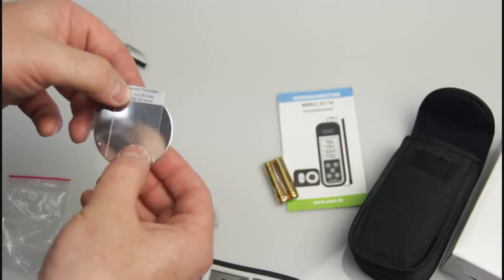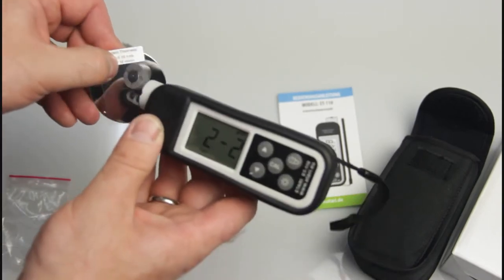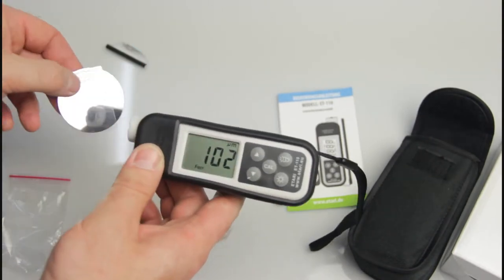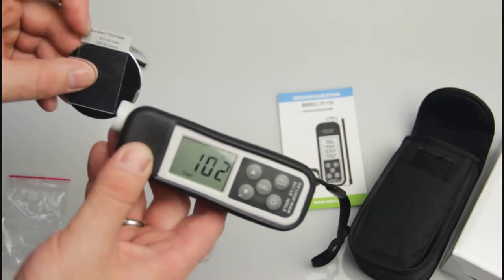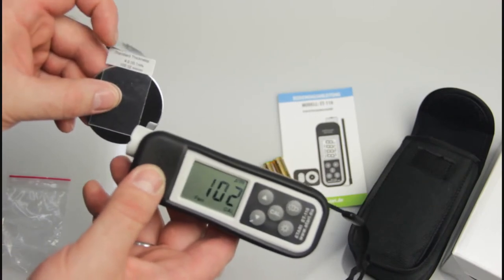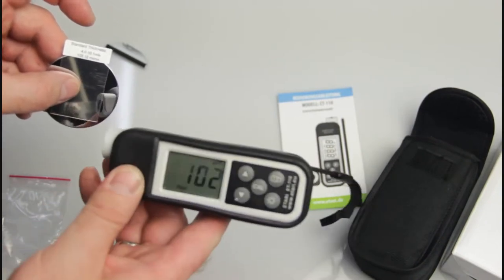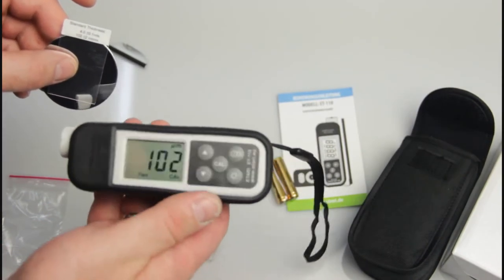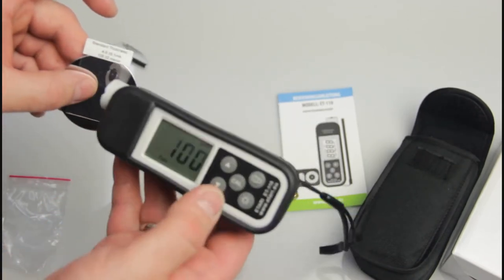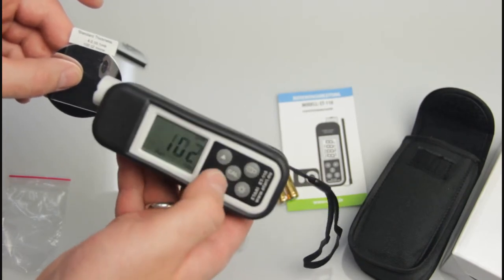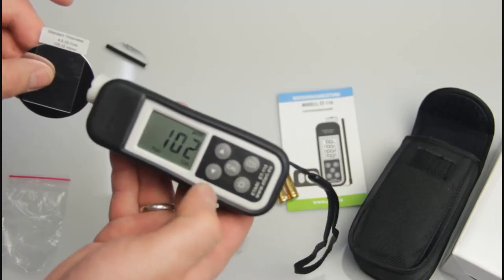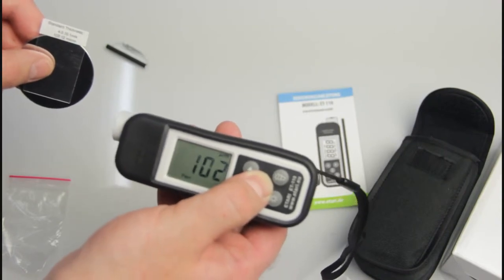Next we have to take the plastic plate, put it on the metal, and measure the thickness of it. As we see it's 102 microns as is set on the plastic plate. It means this gauge is already calibrated. But if it shows not 102 microns, you just turn the arrow buttons to set 102 microns and press calibration button one more time.